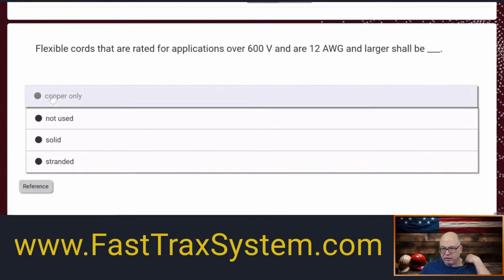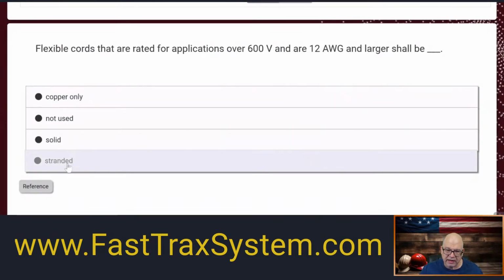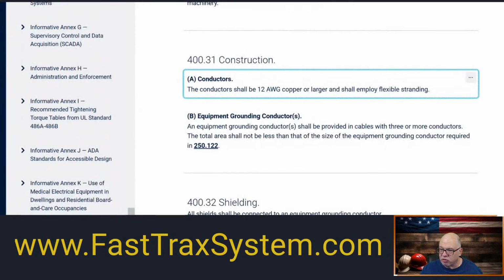So all right, you might say, well, copper only, but then it leaves out the stranding. It seems to me that it's telling me that it should be 12 and larger. So it's talking about the conductor sizing, not the conductor's material. Okay. So if you go back and look at it, the conductor shall be 12 and larger and has to have flexible stranding. Okay. So it just says 12 and larger.